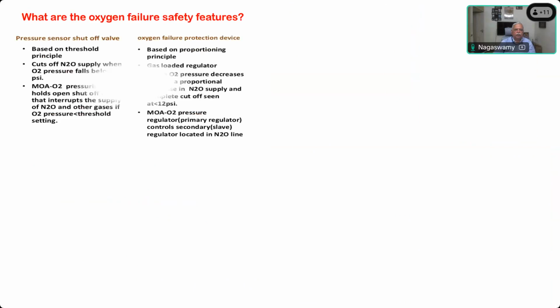What are the oxygen failure safety features? Earlier, sir, we saw only the proportioning system of delivering gases, but if the oxygen totally fails, what are all the safety features to indicate that there is a total lack of oxygen? Oxygen failure alarms. Alarms are there, very good. Oxygen ratio monitor and control, sir.